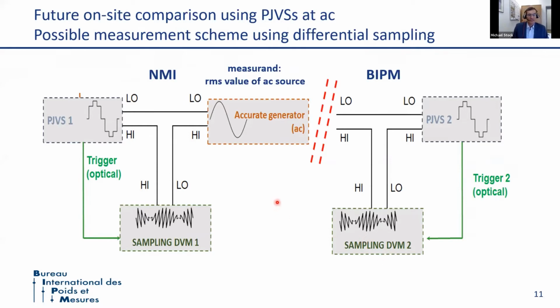The comparison scheme will use differential sampling. The measurement will be the RMS value of an AC source, which you see here, put in opposition with the stepwise approximated sine wave from a PJVS. The difference between those signals resembles what you see here, and is measured with a sampling voltmeter. These measurements are done by the NMI with its own equipment, and by the BIPM with BIPM equipment, which will again be brought to the laboratory of the NMI.